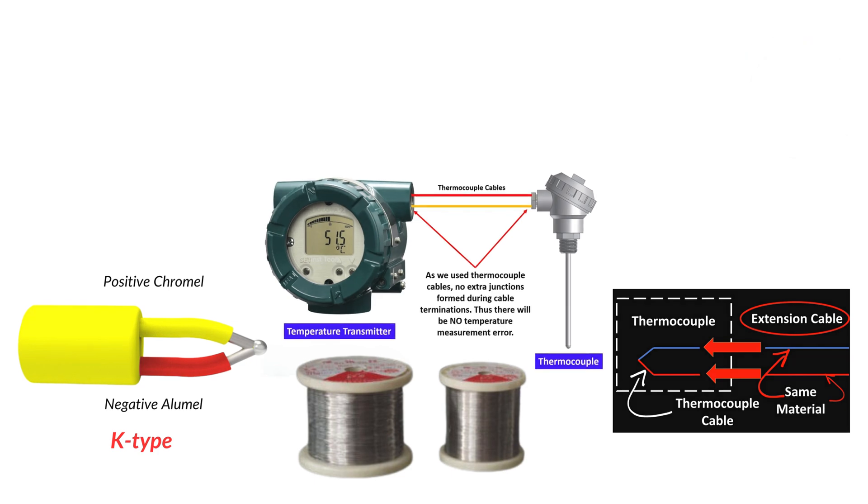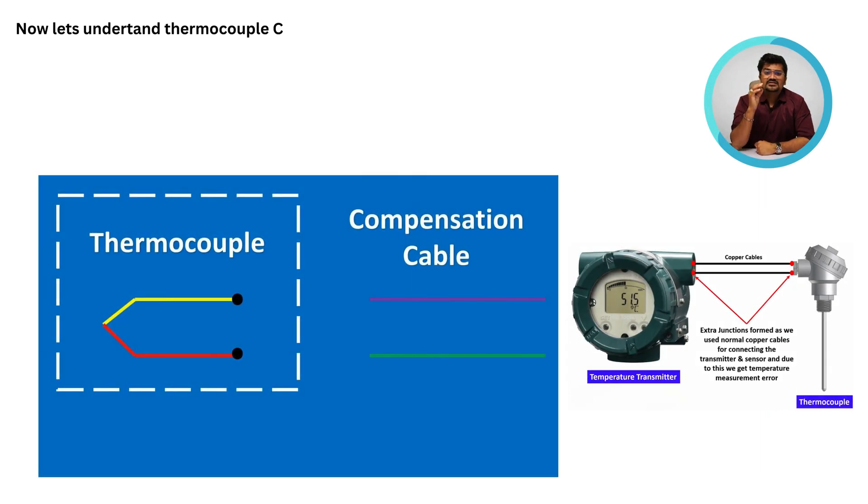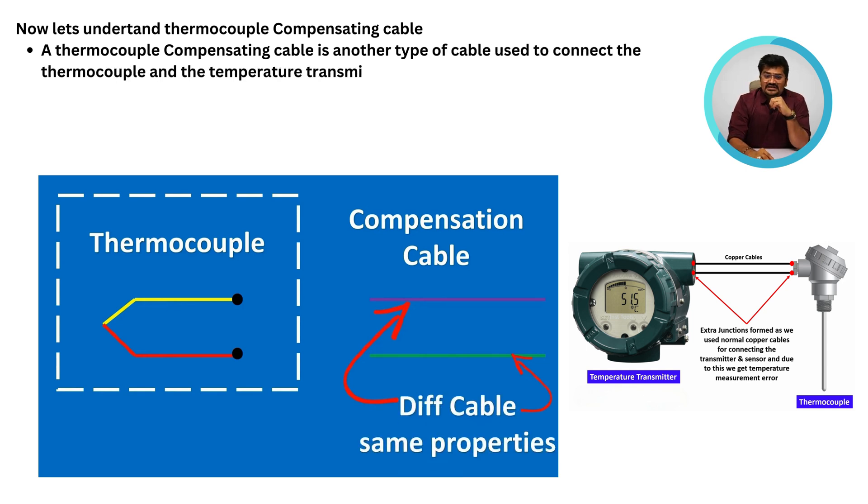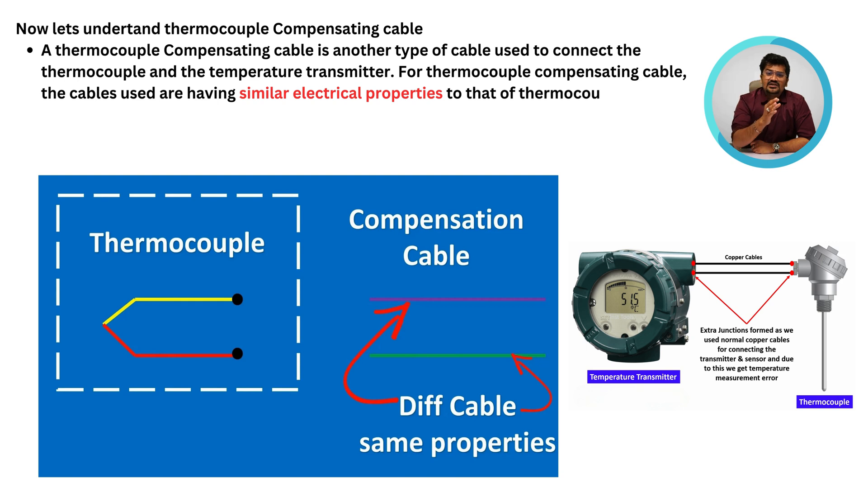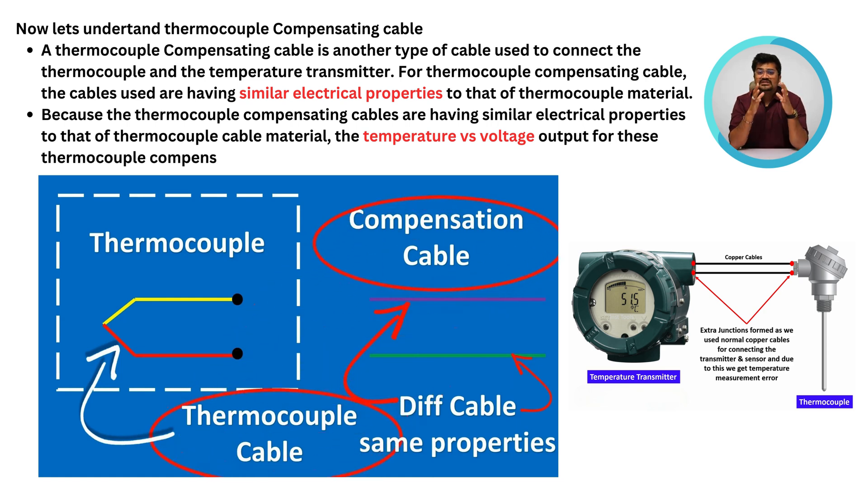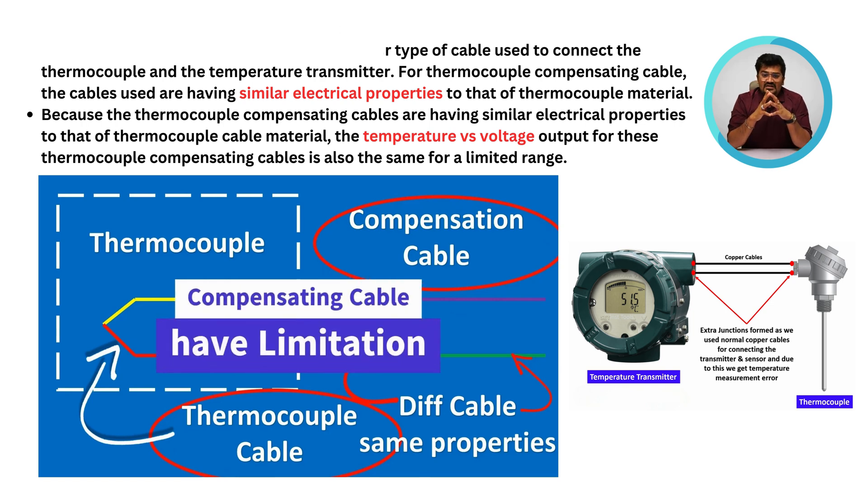Now let's understand the compensating cable. A thermocouple compensating cable is another type of cable used to connect the thermocouple and the temperature transmitter. For thermocouple compensating cable, the cables used have similar electrical properties to that of the thermocouple material. Because the thermocouple compensating cable has similar electrical properties to the thermocouple cable material, the temperature versus voltage output for this thermocouple compensating cable is also the same for a limited range.